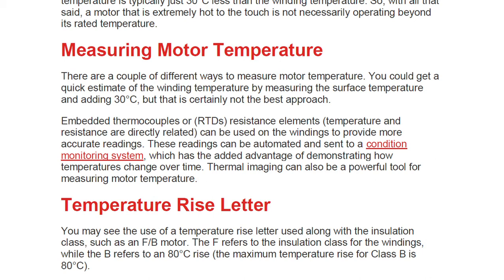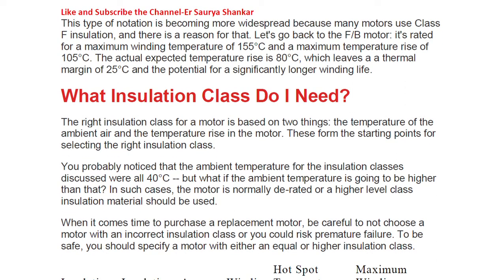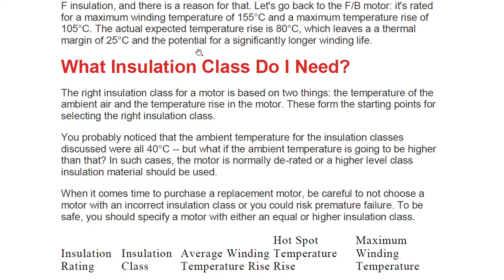You may see a temperature rise letter used alongside the insulation class, such as an F/B motor. The F refers to the insulation class for the windings, while B refers to an 80°C rise — the maximum temperature rise for Class B is 80°C. An F/B motor is rated for a maximum winding temperature of 155°C and a maximum rise of 105°C, but the actual expected temperature rise is 80°C, which leaves a thermal margin of 25°C.